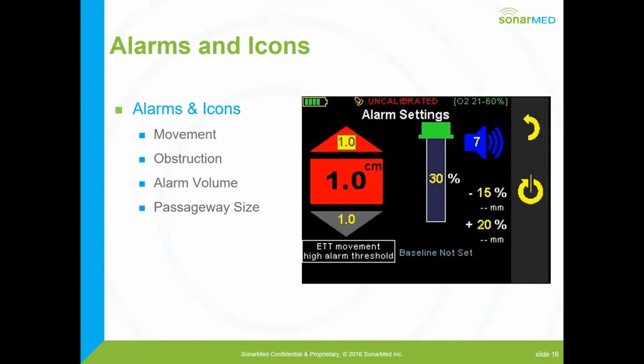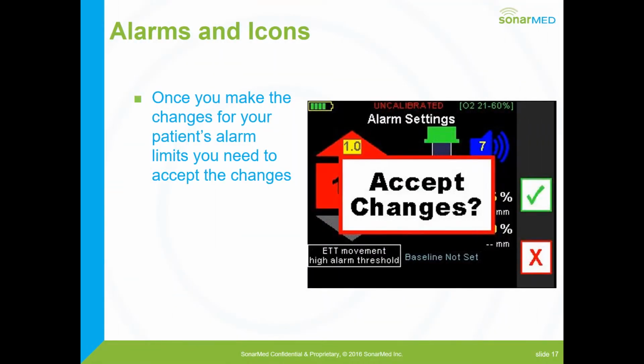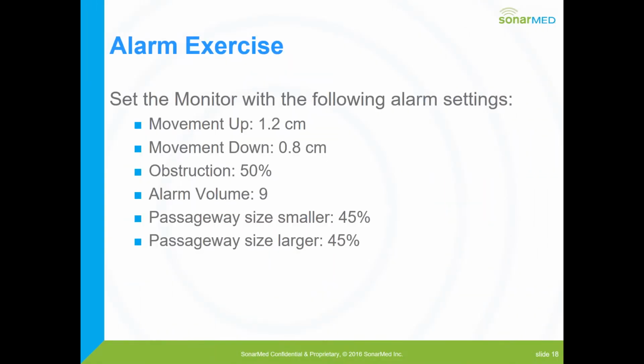Once I've made my changes, and again I use my right, left, up, down navigational buttons, and I center for enter, I want to accept my changes. They are then there. If you have a monitor in front of you, take a minute now to play around with it and set the alarms as you see right here. You want to set movement up to 1.2, movement down 0.8 centimeters, a 50% obstruction, alarm volume at 9, passageway smaller at 45 and passageway larger at 45. I'll give you a few seconds to do that. You can always pause this video as well if you want a little extra time.